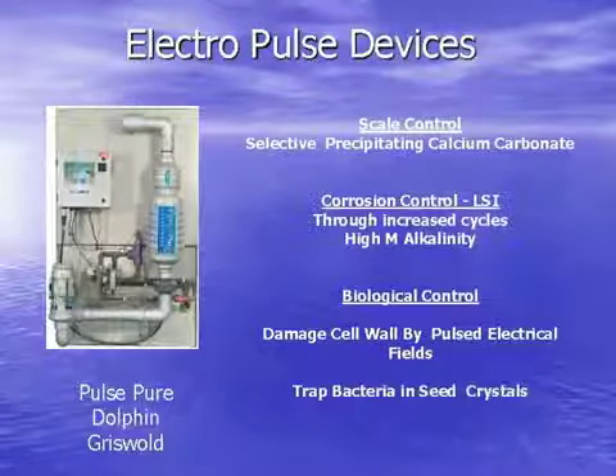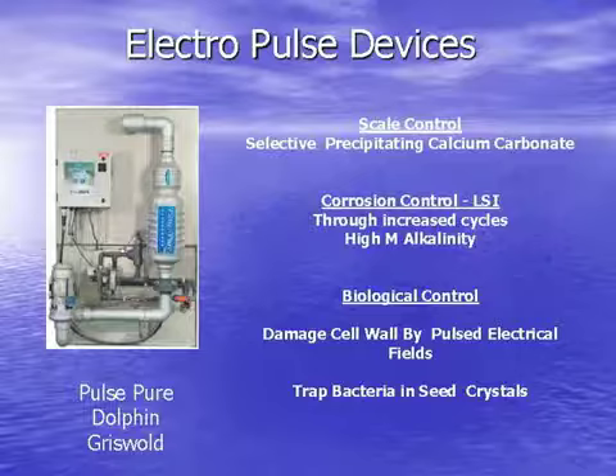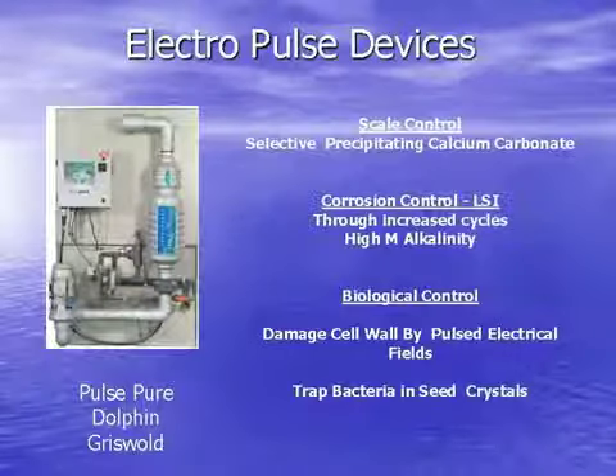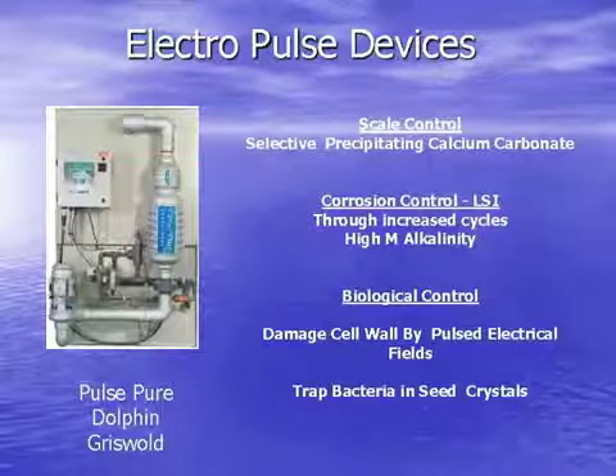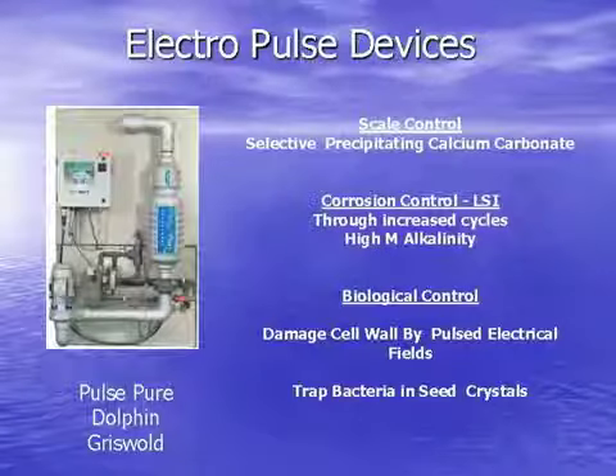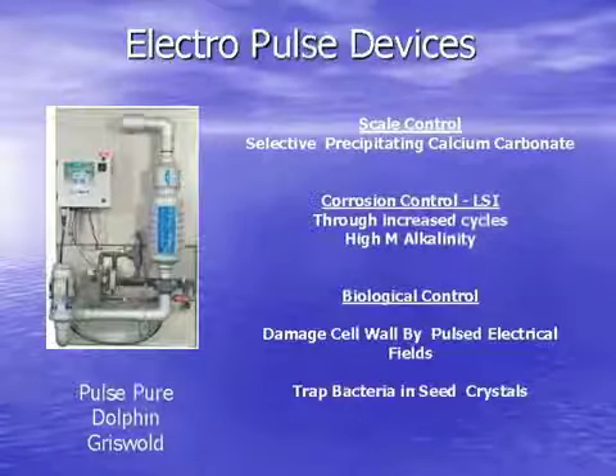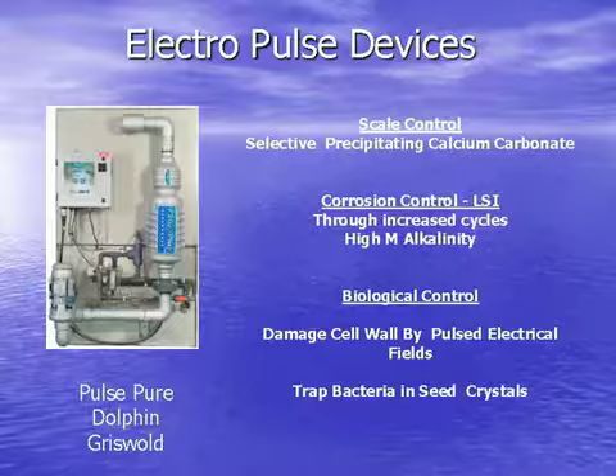Once precipitated, it really doesn't adhere to any heat transfer surface, it's just a particle. So it eventually migrates to the tower basin, precipitates out, and you can remove it through filtration or blowdown. Corrosion control is done through LSI.